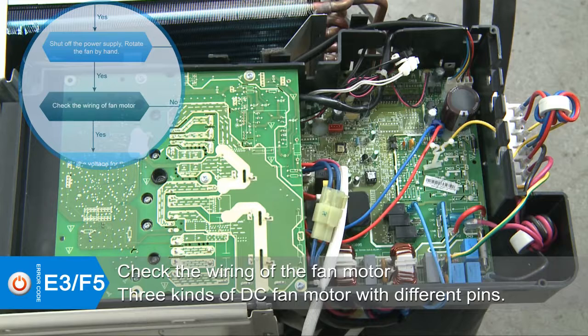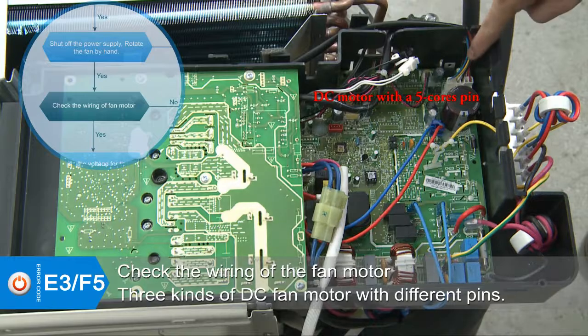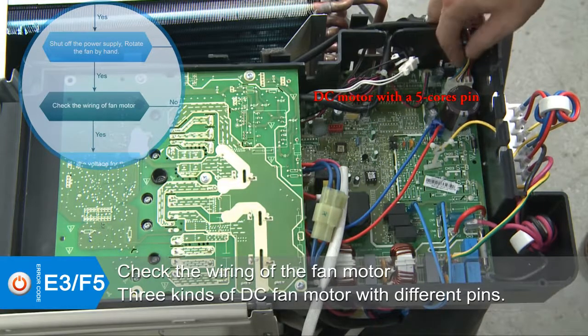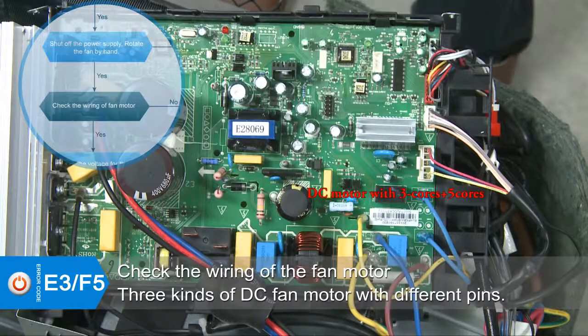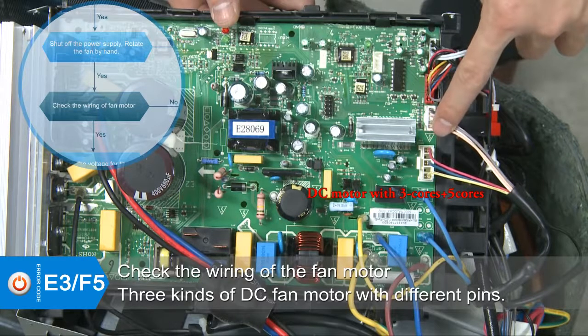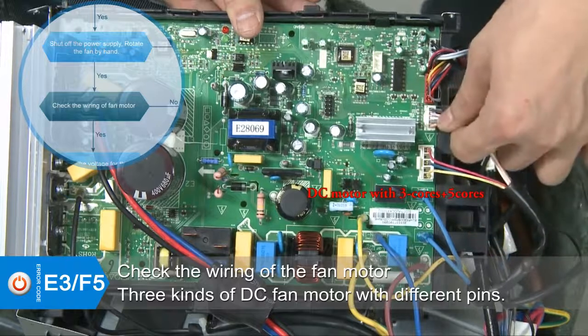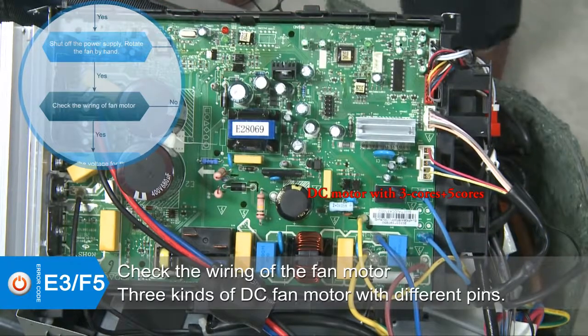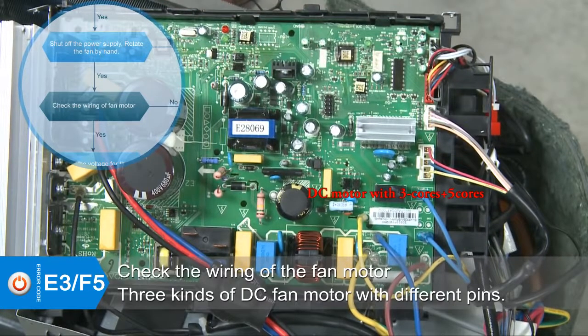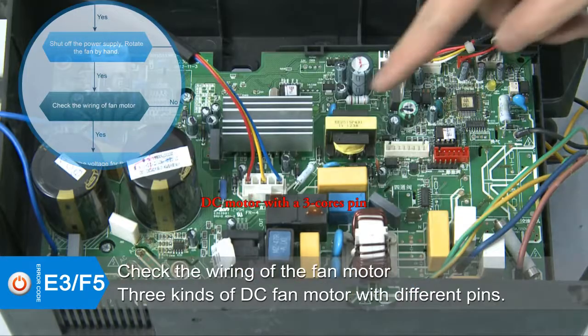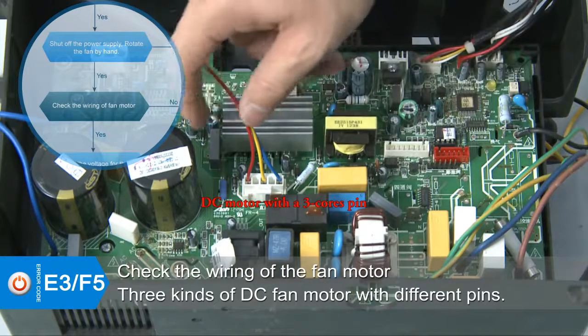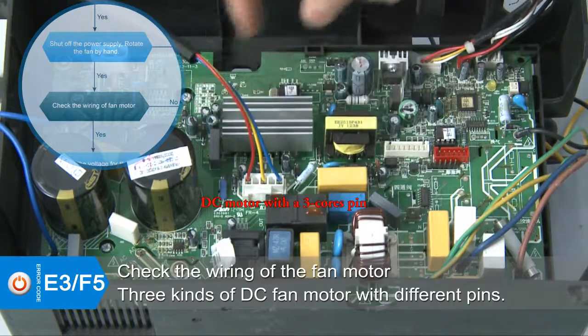Commonly, there are 3 kinds of DC fan motors with different pins. First, a DC motor with a 5 cores pin, which has a control chip inside itself. Second, a DC motor with 2 pins, a 3 cores pin and a 5 cores pin. The control chip for it is on the main PCB board. Separately, the 3 cores pin connects to the power supply, and the 5 cores pin is used for signal transmission. The third, a DC motor with a 3 cores pin, which has the control chip in itself.